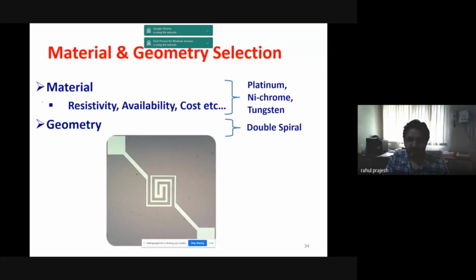Next important point is material—which material you need to use. Before you freeze your material, you need to consider its resistivity, which should be high, because only a resistive metal will offer heating characteristics. Then consider availability, cost, and physical or chemical stability. Considering all these parameters, there are a few choices: platinum, nichrome, and tungsten. These are the best possible choices for a microheater.